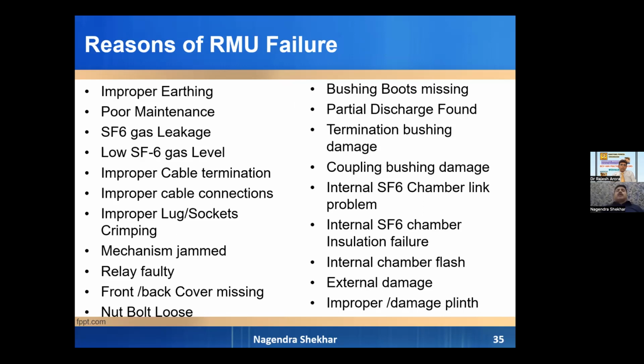So why do RMUs or switchgears fail? First of all, improper earthing. Earthing is not proper, so the load current takes another route. Poor maintenance, which is obvious. SF6 gas leakage, low level of SF6 gas, and we operate it. Improper cable termination, where the load of the cable is on the termination bushings, and the gas leaks from that. Improper size of lugs and sockets, or improper crimping. Mechanism of switchgear is jammed and we try to operate it forcefully.